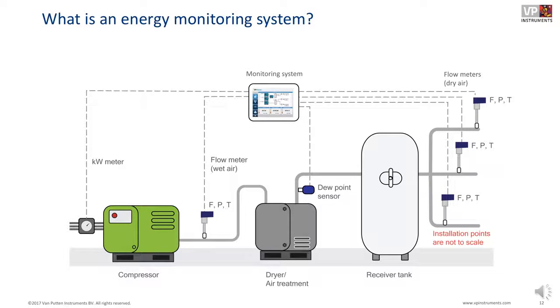We connect a kilowatt meter, which is communicating 4 to 20 milliamp, and we connect it directly into the computer. There is an analog module that receives about 8 channels of analog signals. In this example, we now use 2, one for kilowatt and one for the dew point sensor we actually see after the dryer. We are also measuring wet air out of the compressor. This is the Flowscope DP, our differential pressure meter, which is capable of measuring saturated and hot air. We connect that through the Modbus RTU connection.